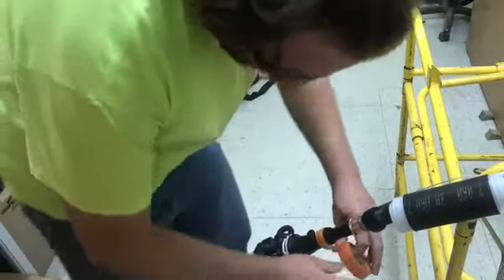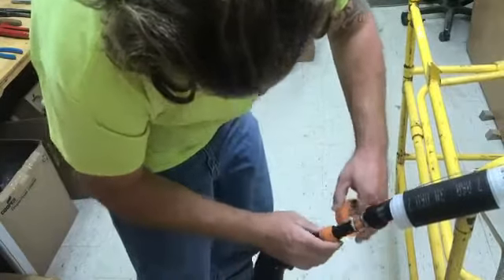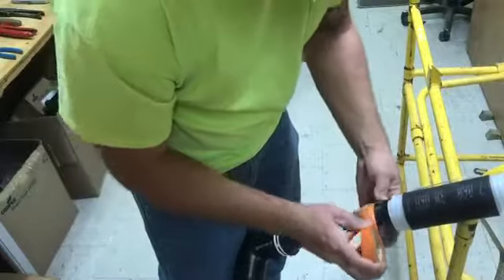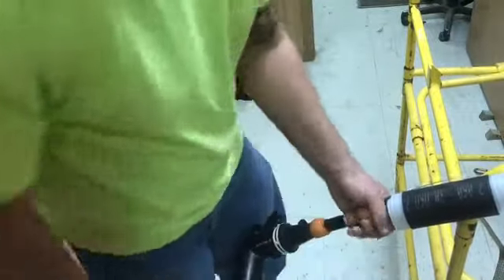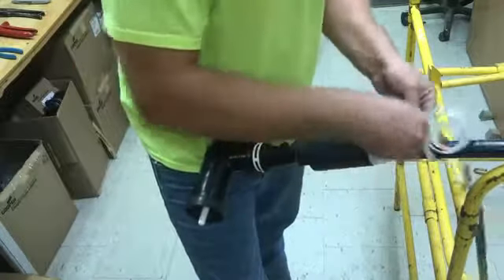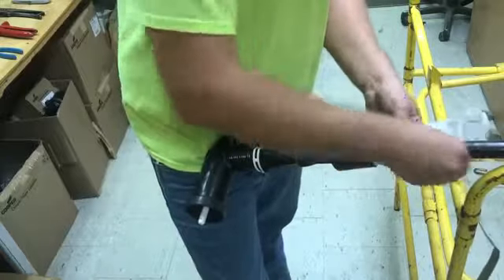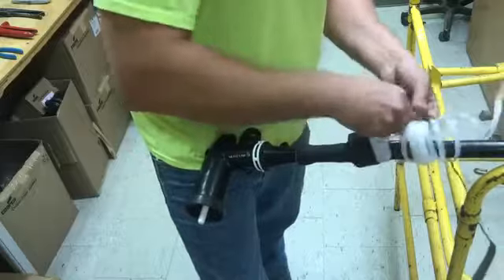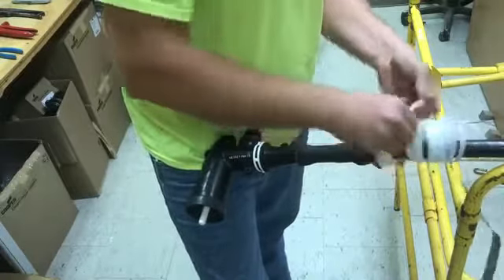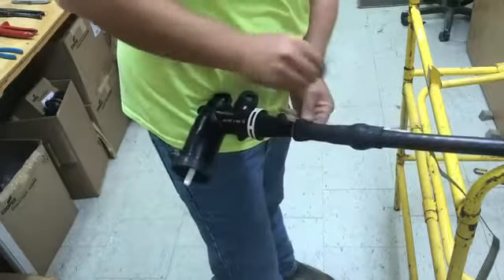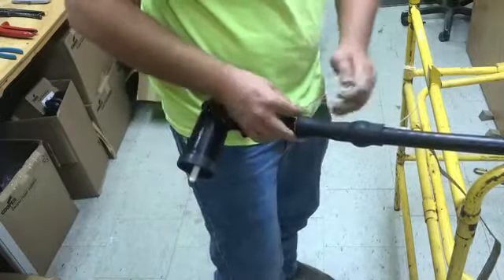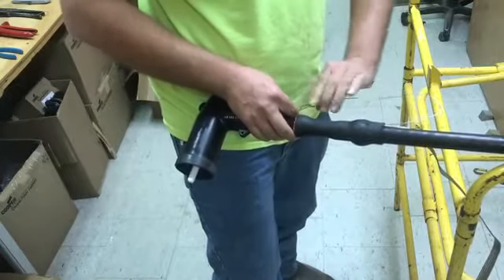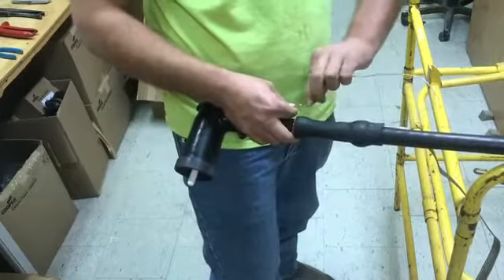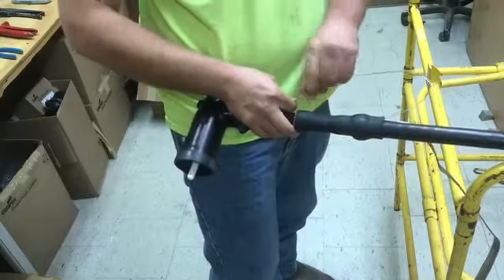Secure and protect your sealing mastic from the cold shrink tube with one wrap of vinyl tape. Install the cold shrink tube beginning on the leading edge of the 200 amp boot sealing mastic. Finally, install the static ground onto the back of the boot, twist the wire, and trim off excess. This is a completed Cooper 200 amp loadbreak elbow.